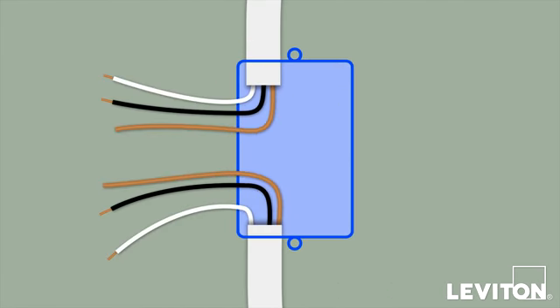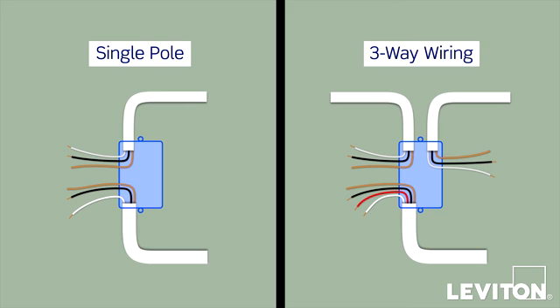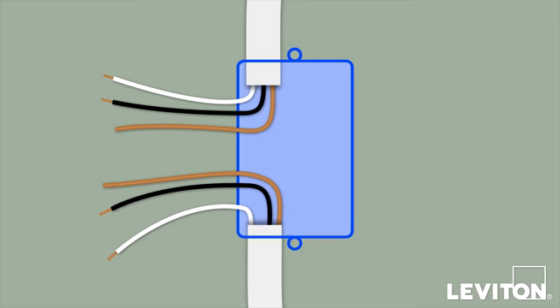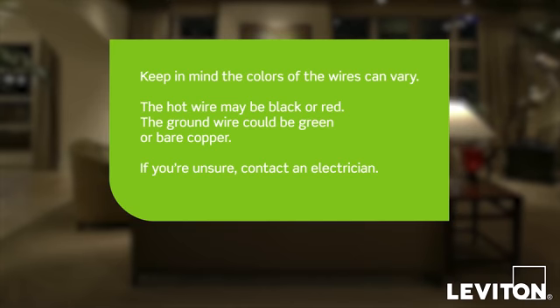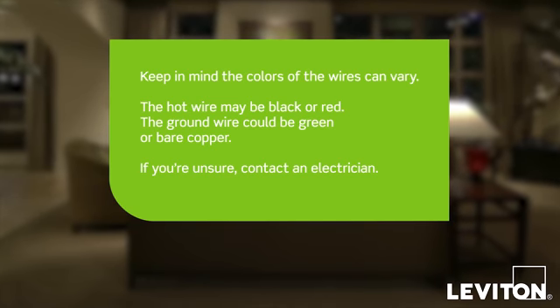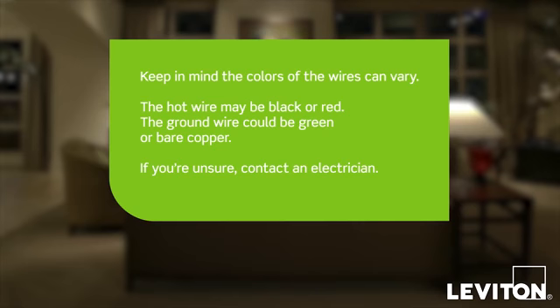Straighten out and separate each wire so that you can clearly see them. Make sure that none of the exposed metal ends of the wires are touching each other. Identify whether the wiring application is a single pole or three-way application. If wiring in the wall box does not resemble either of these configurations, consult an electrician. Note that in this example, there is a black hot line wire, a black load wire, two white neutral wires, and a bare copper wire, which is the ground. Keep in mind the colors of the wire can vary. The hot wire may be black or red. The ground wire could be green or bare copper. If you're unsure, contact an electrician.